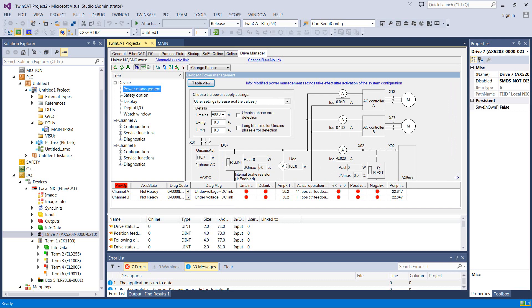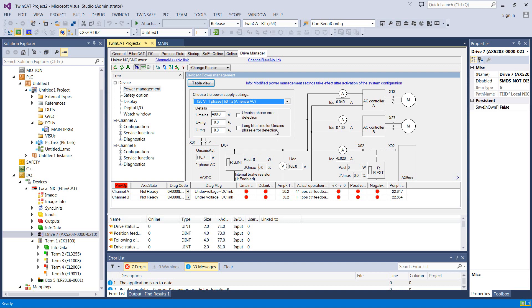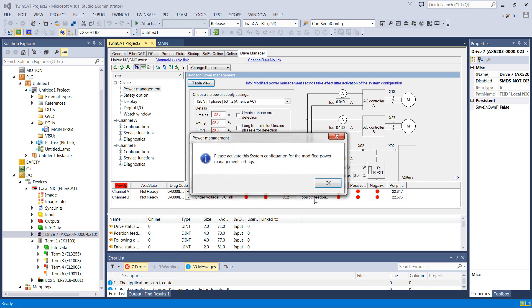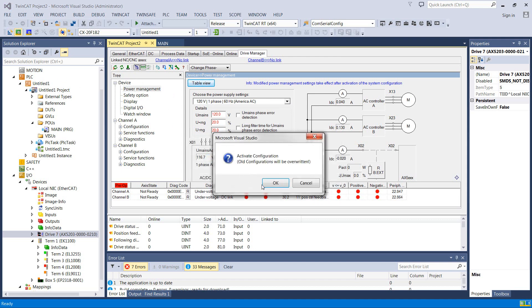So it's set up for 400 volt, which is not what we're running, so let's go ahead and fix that to 120 American AC. That's what we've got, and we'll go ahead and download it, and it says we've got to activate to change power settings. Not all settings you have to activate for, but this is a pretty big one, so let's go ahead and do that.